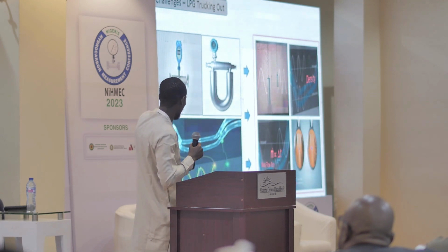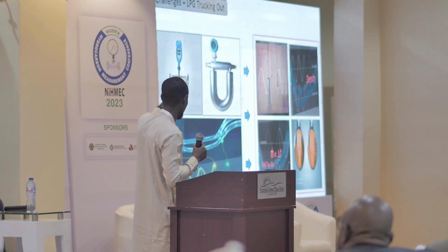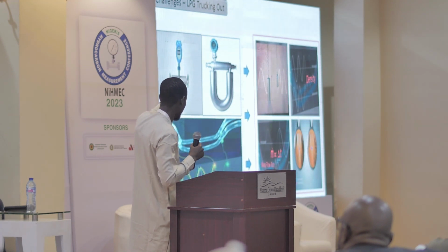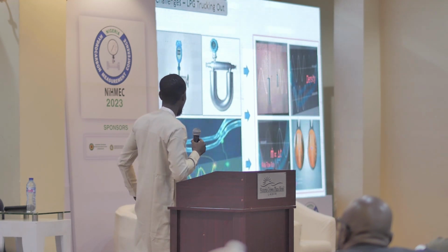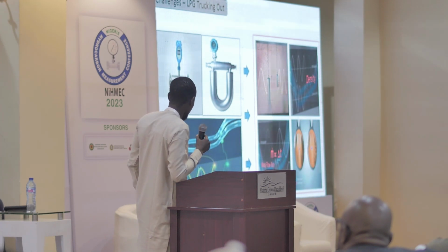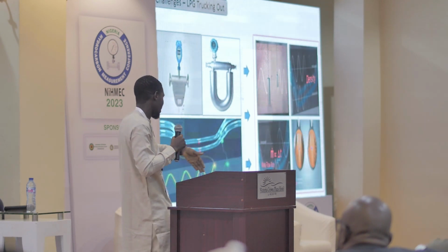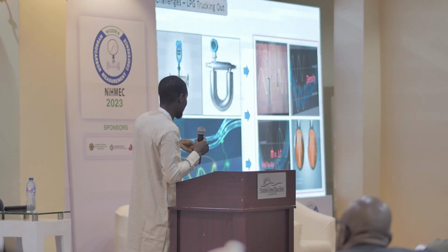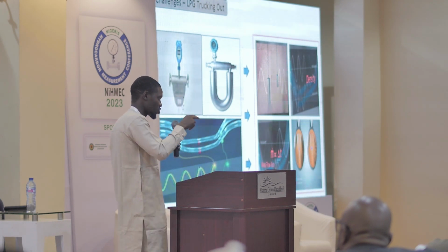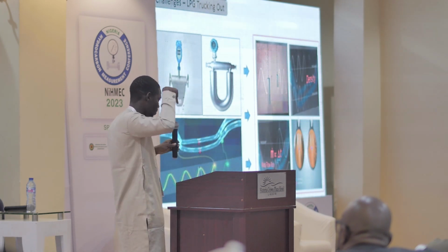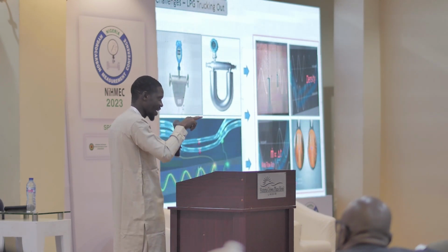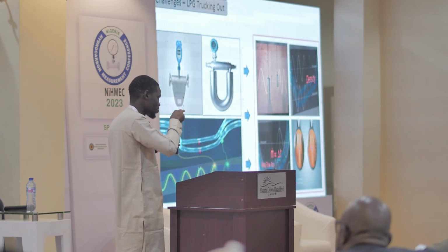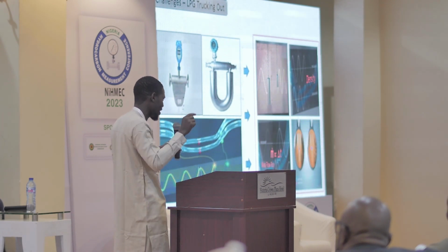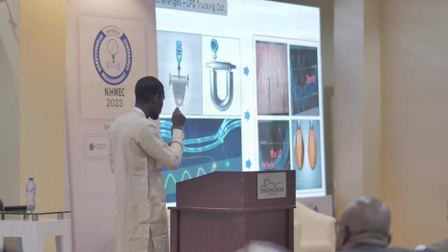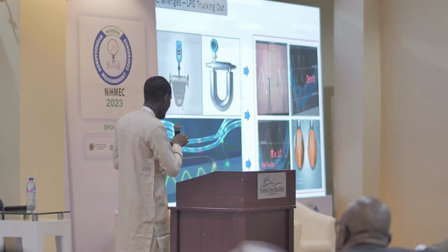So we have this Coriolis flow meter, Endress and Hauser. Sorry, the gantry is Emerson, and then we have Endress at the jetty. The principle of this Coriolis flow meter is you have a sensor at the inlet, and another sensor at the outlet, and then you have an exciter at the center. And this tube that goes through your flow meter, when your gas is passing, it usually swings. And this sensor senses how the tube swings, and that gives you your mass totalizer, so metric ton per hour, so kg per hour. But the problem is this.